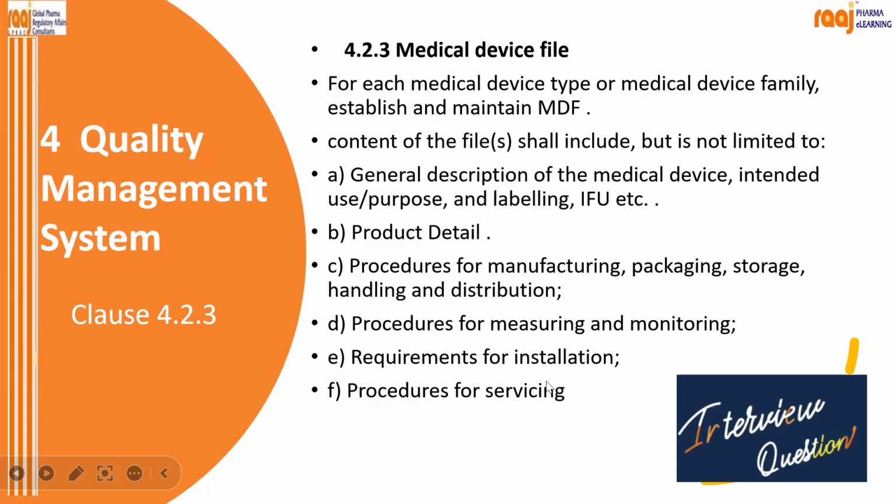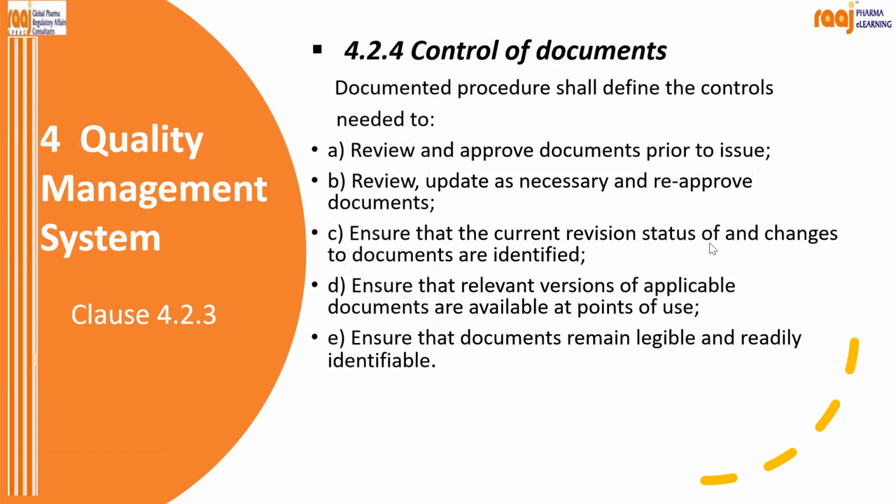So these two parameters, installation and servicing, are applicable only in case your device is installed in the hospital, like an X-ray machine, CT scanner, MRI scan. In that case also, it is applicable for equipment. But if it is only a medical device, only A, B, C, D is applicable. E, F is applicable only in case of installable equipment.